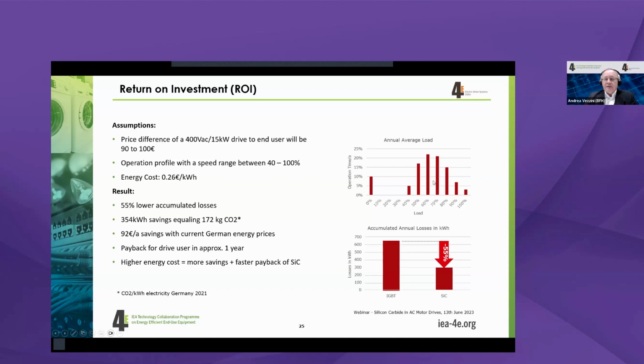And if you take this into account, you have to then look at the efficiencies at these different speeds, look at the energy which is turned over at these speeds, and look at the savings you have, multiplied with the electricity cost in Germany in 2021, which is 0.26 euro. You would have then total annual accumulated losses, and you have this for silicon and silicon carbide, and you have a reduction of roughly 55%. Meaning, because especially in the part load range here, we have efficiency gains, we can then look at these gains and see what did we actually save.